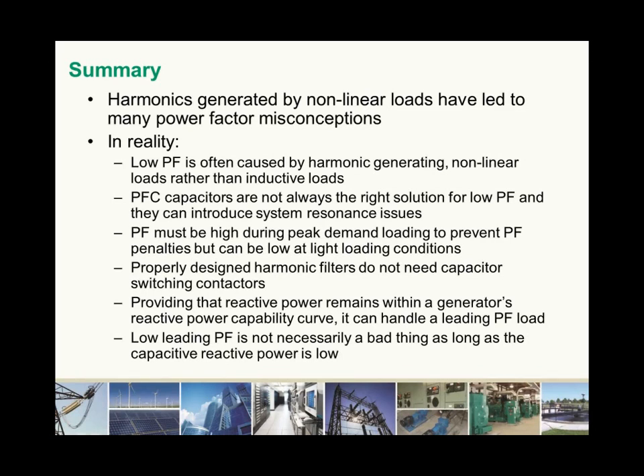Properly designed harmonic filters do not need capacitive switching contactors. Providing that reactive power remains within a generator's reactive power capability curve, it can handle a leading power factor load. And finally, low leading power factor is not necessarily a bad thing, as long as the capacitive reactive power is low.